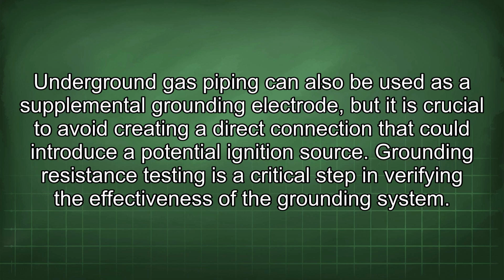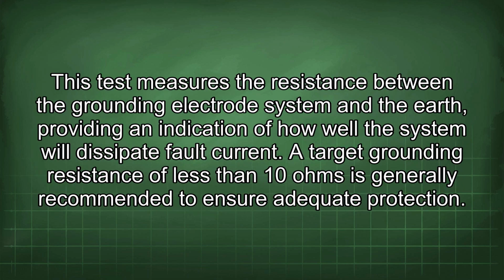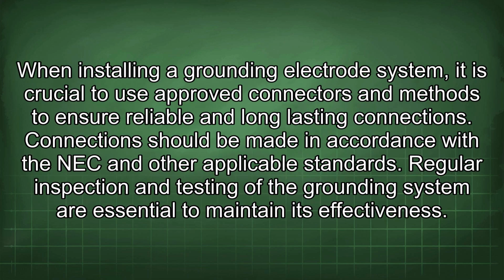Grounding resistance testing is a critical step in verifying the effectiveness of the grounding system. This test measures the resistance between the grounding electrode system and the earth, providing an indication of how well the system will dissipate fault current. A target grounding resistance of less than 10 ohms is generally recommended to ensure adequate protection. When installing a grounding electrode system, it is crucial to use approved connectors and methods to ensure reliable and long-lasting connections. Connections should be made in accordance with the NEC and other applicable standards.